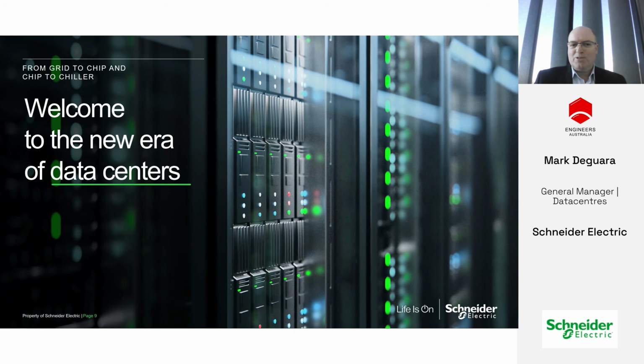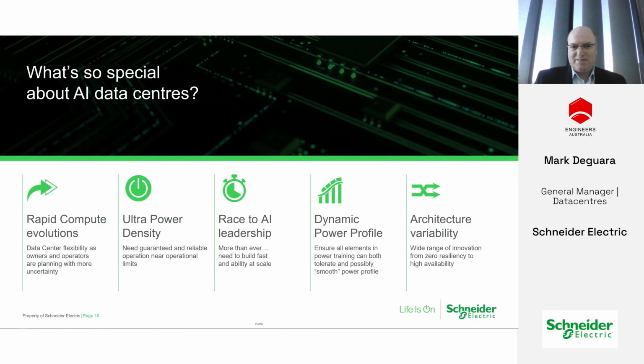Welcome to the new era of data centers. So what's so special about an AI data center or a high performance compute data center? Rapid compute evolution. I recently spoke about capacities going from 10 kilowatts a rack, to 100, to 150, to a megawatt, potentially 2 megawatts a rack. That's significant, and it's happening within a 6, 12, 18 month period. It's not happening over 5 years.